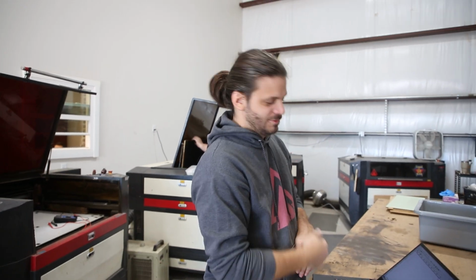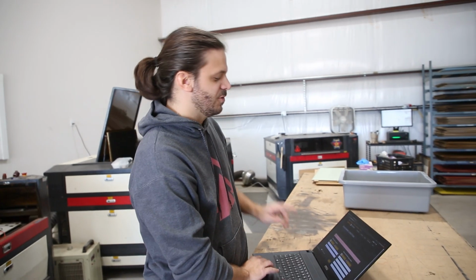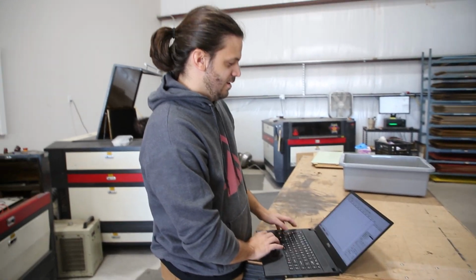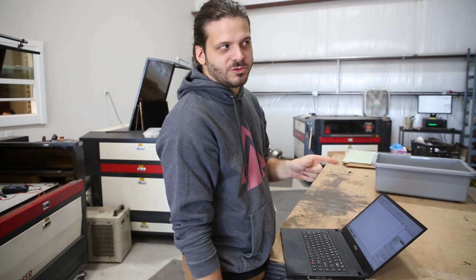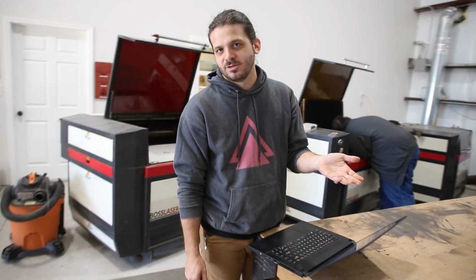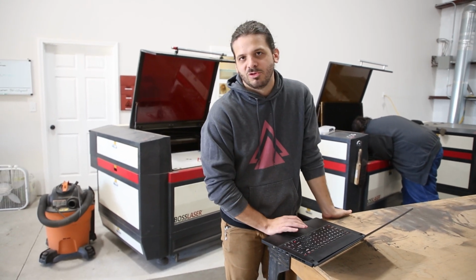So what you're saying is we're going to bypass any safety function the machine has. Yeah. Well, specifically, we're going to bypass the magnet latch and the chiller, and then try to run the machine. If the machine runs with those bypassed, we know for sure one of those is the issue. At which point we can turn on the magnet latch and run it—if it works, then it's the chiller. Or we turn on the chiller and run it—if it works, then it's the magnet. We at least can isolate the problem at that point.